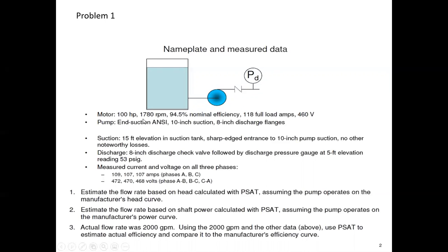Okay, so nameplate stuff, 100 horsepower motor, rated speed when the motor is putting out 100 horsepower is 1780 RPM. The nameplate nominal efficiency at full load would be 94.5%. Full load amps are listed at 118, and all this rating goes on at 460 volts. It's an end-suction ANSI pump. That's a pull down from PSAT, and the suction pipe is 10 inches, and the discharge pipe on this side is 8 inches. Basically, that's what that's telling you.